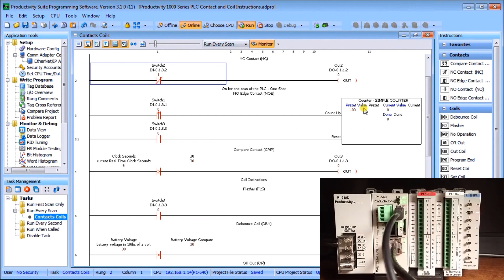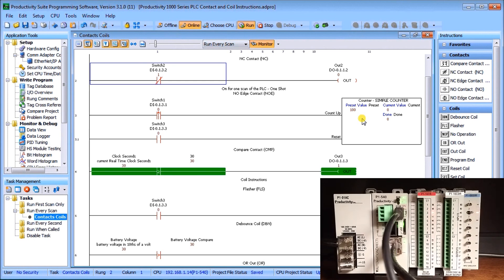That is my differentiate up instruction. If I did not use differentiate up, it would count on every single scan of the PLC, so I would have a number that continuously rolls around. When you are programming, just remember that a one-shot is the way to go in order to solve that scenario.